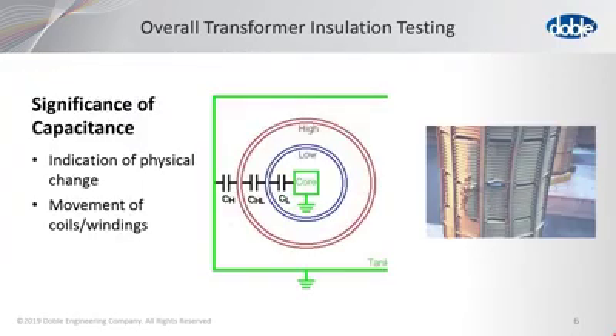One significant thing that we found also is that the capacitance of these overall tests indicates the physical orientation of the windings, and it can easily detect movement of the coils or the windings. You can see on the right-hand side of the screen here that there is a winding with an inward buckling that was identified by the overall test.